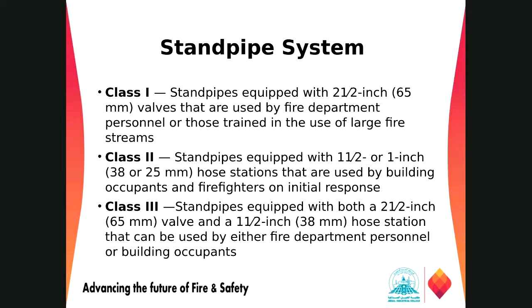Class 1 is mainly used by the fire department team. No one can use that other than the fire department teams. Class 2 systems can be used by some trained persons inside the building, like inside the occupancies or inside the healthcare occupancies. There is some fire watch team who has the knowledge to use this, so they can use this kind of equipment. And class 3 is the combination of these two.